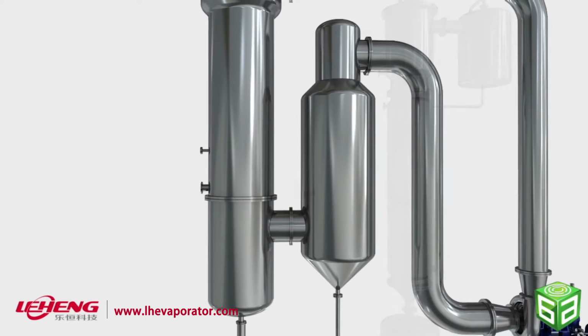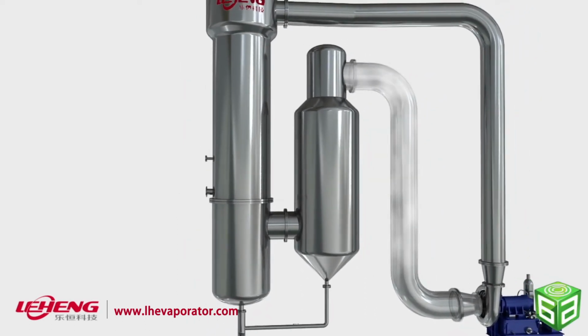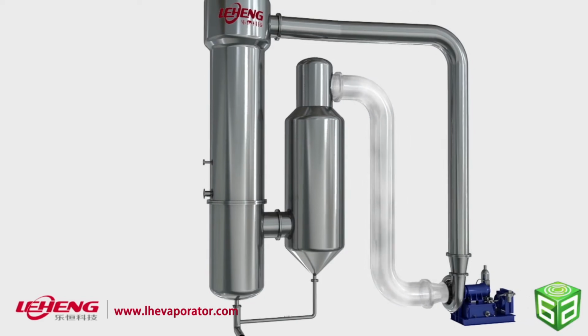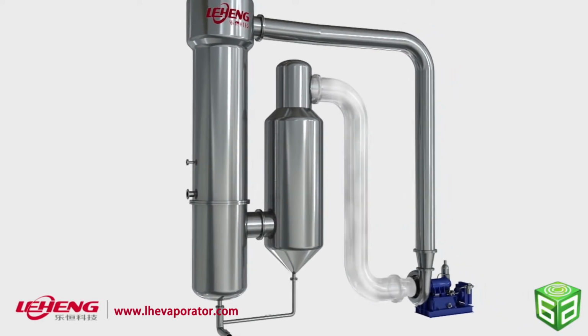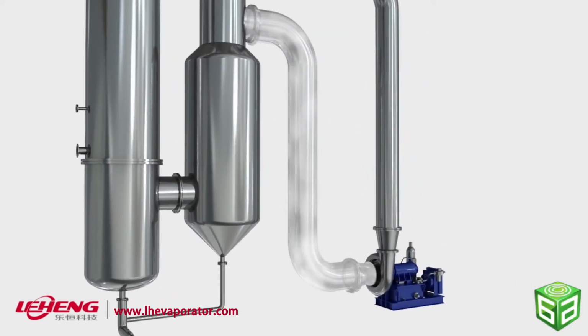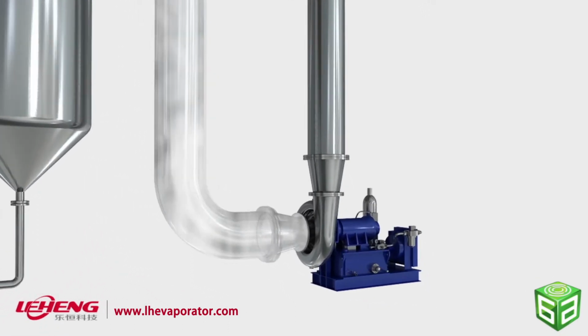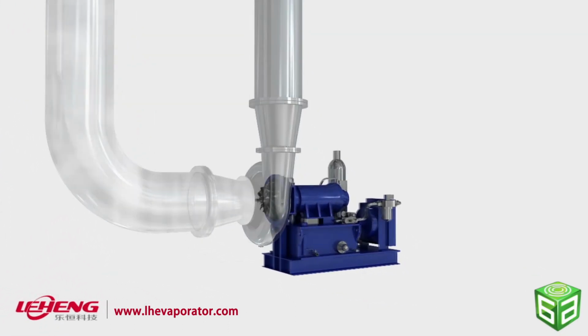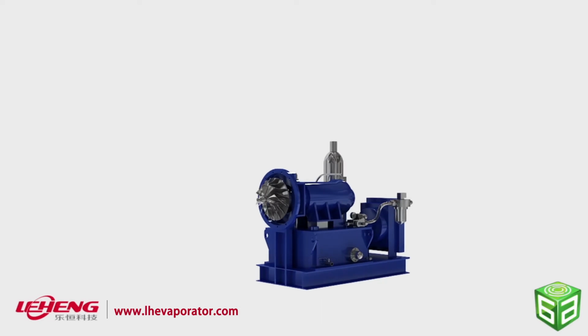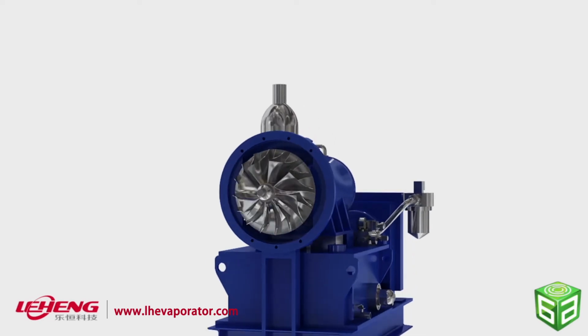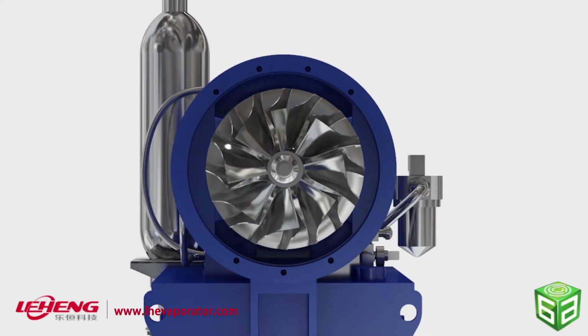Steam is generated through the liquid evaporation process and flows into the direct drive centrifugal steam compressor after leaving from the top of the separator. The direct drive compressor is driven directly by an electric motor with a rotating speed between 30,000 rpm and 40,000 rpm, without a gearbox being required.